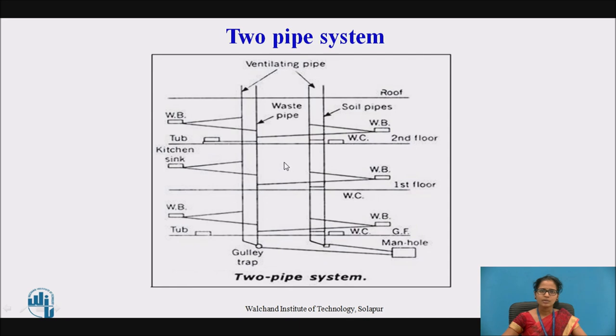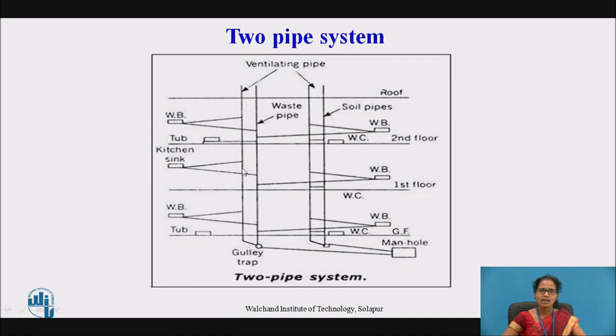The two pipe system consists of two vertical pipes — two separate pipes are provided. One pipe is for collecting waste water, called the waste pipe. The second is the soil pipe, which includes discharge material from water closets and urinals. The soil pipe is connected to the drainage system or manhole, whereas the waste pipe is connected through a gully trap. The traps of the WCs and wash basins are connected to the soil pipes, while the traps of wash basins and kitchen sinks are connected to the waste pipe.